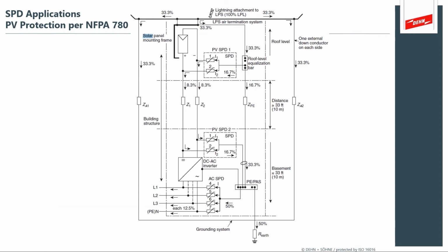And this is directly drawn from the NFPA 780, and this is for solar power PV protection. What you see is the application of SPDs at several locations within the structure. This is an introduction to that concept of coordinated systems where you've got SPDs out at the actual solar panel frame and SPDs located at the combiner circuits, the inverter circuits, and then again, surge protection devices on the AC side. The only thing that's missing from this particular sketch is the surge protection devices on the data networks that are also probably coming into the building structure.